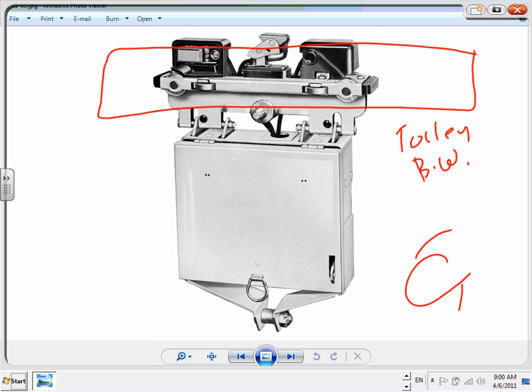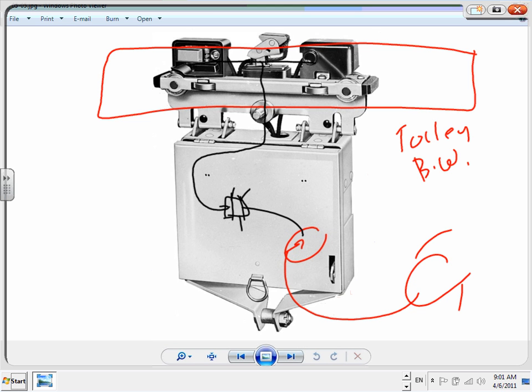If I have a machine right here, I wire it. Here's my plug, and out of this plug I need to fuse it. This is my fuse, and from here it's tied to the busway and moves with it. There's an SO cord coming down to feed the machine, and there's a plug. Why do you think we have a plug here? Disconnect, thank you. Otherwise, if you don't have a plug, you have to have a disconnect, because that's a machine. The plug acts as your disconnect. You can unplug it and the machine is dead if you were to maintain the machine.